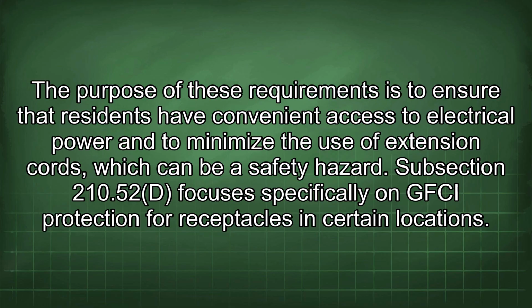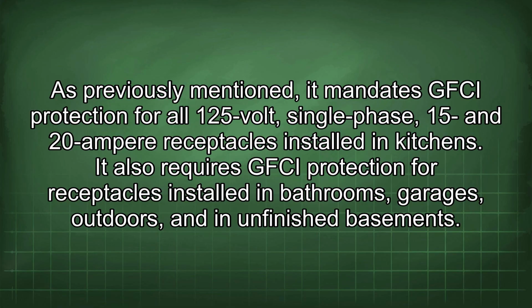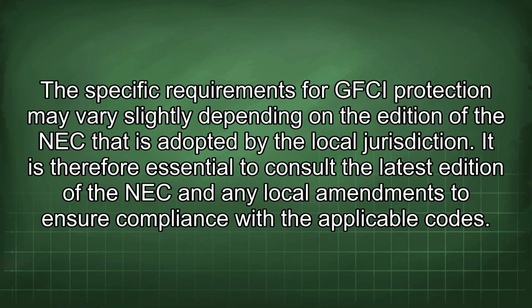Subsection 210.52(D) focuses specifically on GFCI protection for receptacles in certain locations. As previously mentioned, it mandates GFCI protection for all 125-volt, single-phase, 15 and 20 ampere receptacles installed in kitchens. It also requires GFCI protection for receptacles installed in bathrooms, garages, outdoors, and in unfinished basements. The specific requirements for GFCI protection may vary slightly depending on the edition of the NEC that is adopted by the local jurisdiction. It is therefore essential to consult the latest edition of the NEC and any local amendments to ensure compliance with the applicable codes.